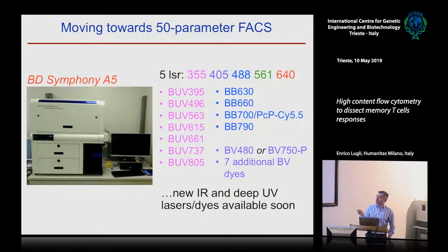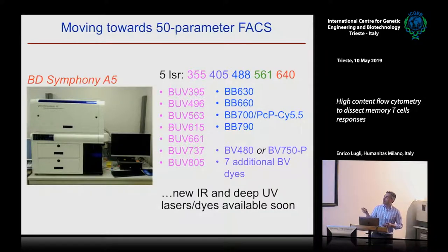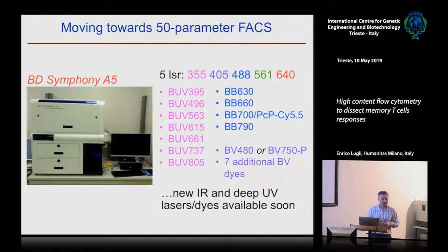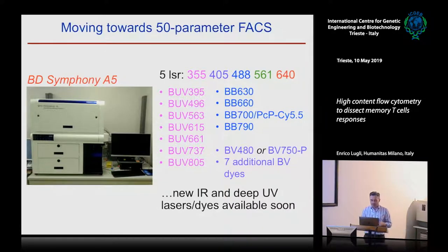This instrument is from Becton Dickinson — the Symphony A5. There are also other instruments like Biorad that can measure up to 30 parameters. This instrument has the usual lasers: 405, 488, 561, and 640 nm. We added a UV laser, which excites seven new conjugates — new fluorochromes we could add to our array. Then there are other synthetic fluorochromes — the so-called brilliant blue dyes — like a bright replacement for PerCP-Cy5.5, which is a bit weak, and molecules like BV480 and BV786, etc. This machine will also be modified by integrating new infrared and deep UV lasers. There are already 10 to 15 fluorochromes ready to be excited by these lasers, with the idea to jump from 30 to 45 or 50 parameters in the next couple of years.